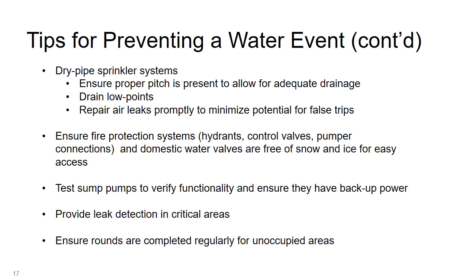These should be tested before heavy rainfall events, before spring snow melts, and if any sprinkler testing discharges water within the building, such as parking garages. Leak detection that's tied into a building automation system is an excellent warning method for water being in areas where it shouldn't be. Typically, server rooms will have leak detection below raised flooring. Another example is diesel generator rooms. They'll have leak detection around tanks and piping. And other critical areas may have leak detection as well.